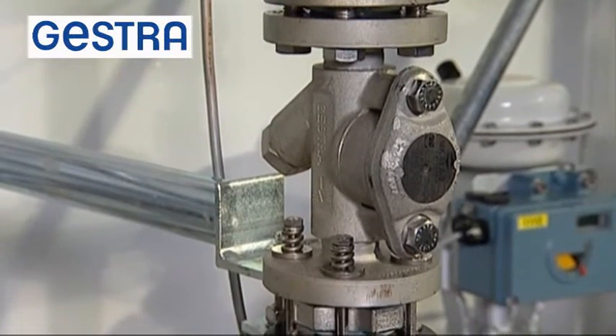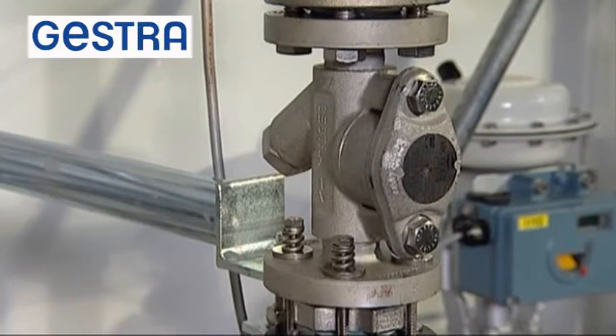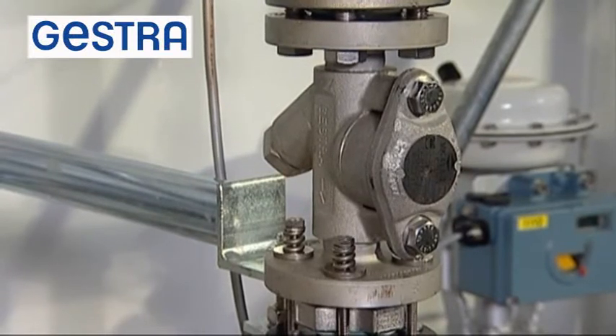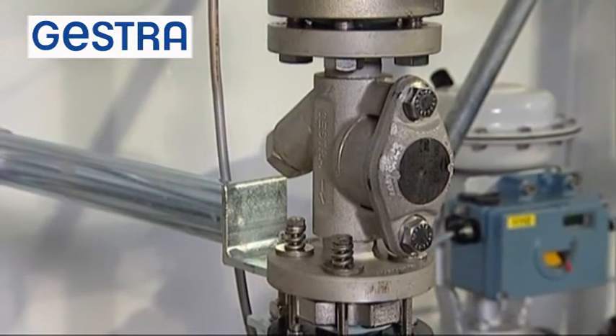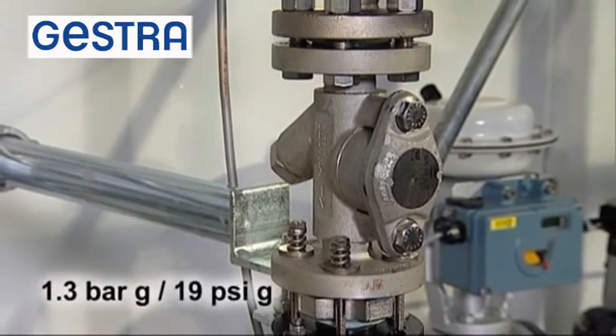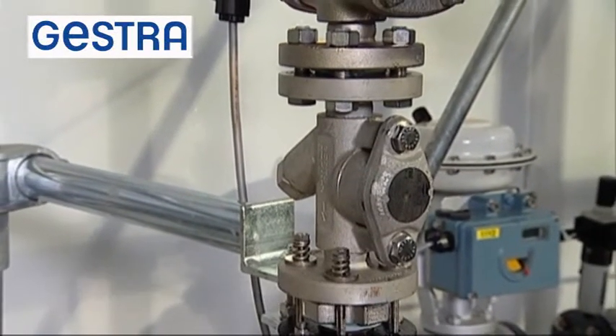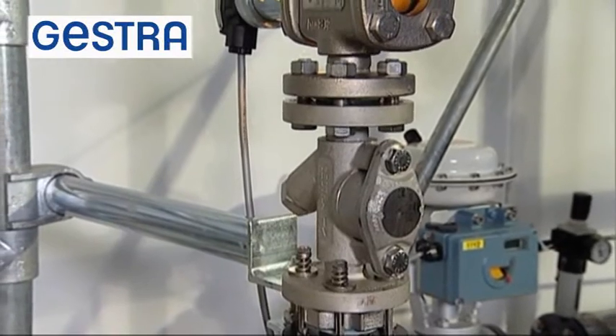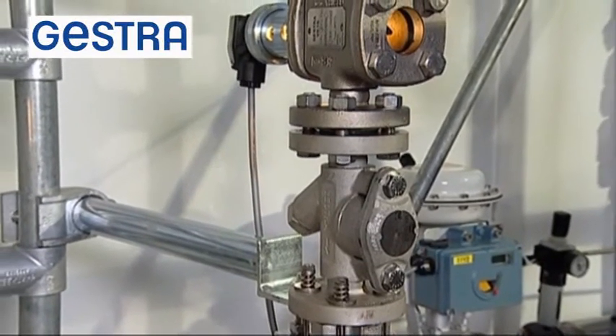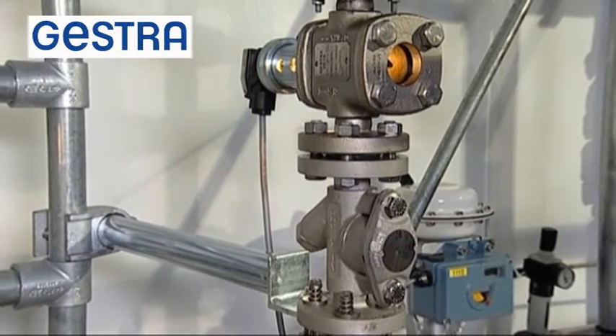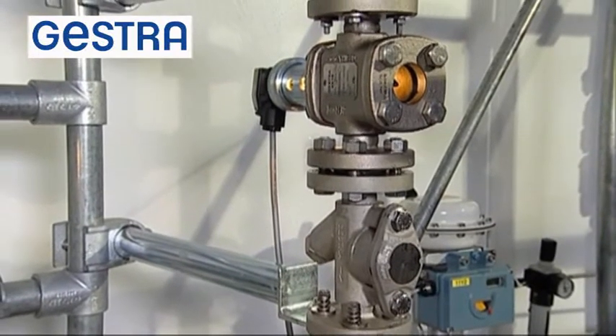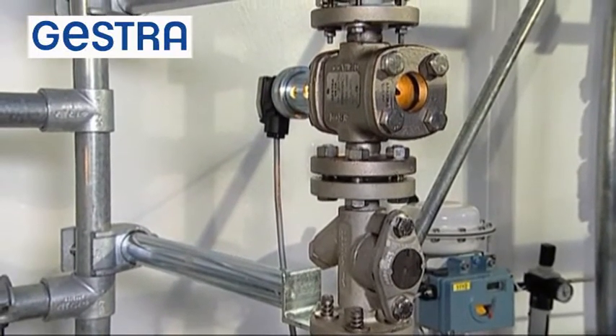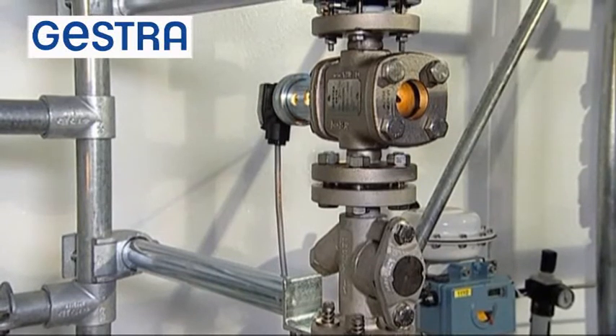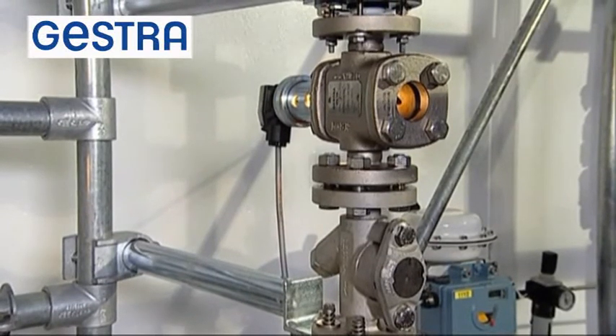We shall now consider the membrane steam trap that is installed in the vertical line. This is the same type. The operating pressure has again been set to 1.3 bar G. The condensate can now flow into the steam trap from the top down. The body of a thermostatic steam trap should not be insulated, since this would impair the control accuracy.